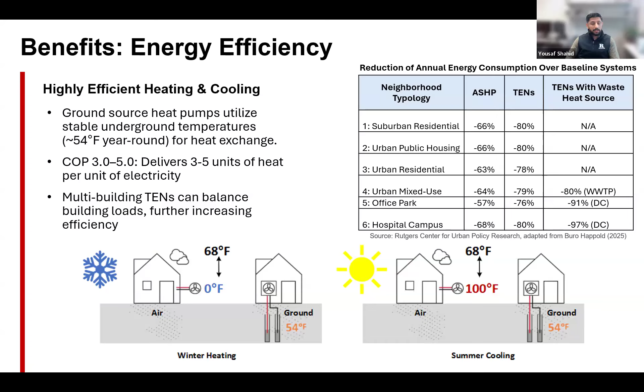When you look at the table on the right, you can see what translates that into practice. TENS reduces annual energy consumption by 76% to 80% below baseline across all typologies, consistently outperforming air source heat pumps. And when the waste heat is added, some typologies push even further. The hospital campus scenario, for example, hits a 97% reduction with a data center source, which is a big number in terms of overall energy reduction.